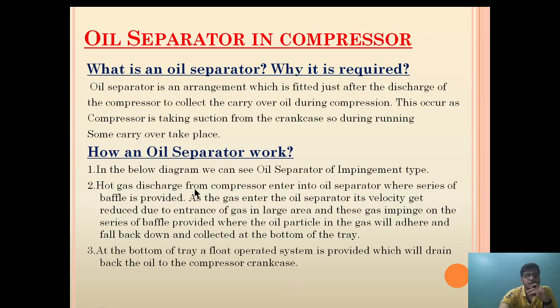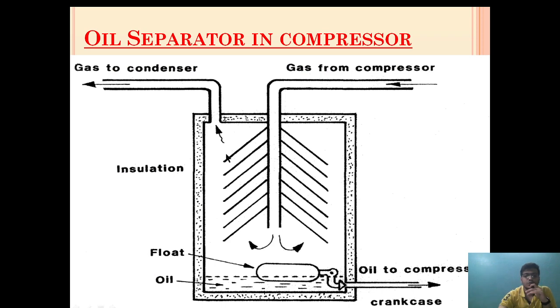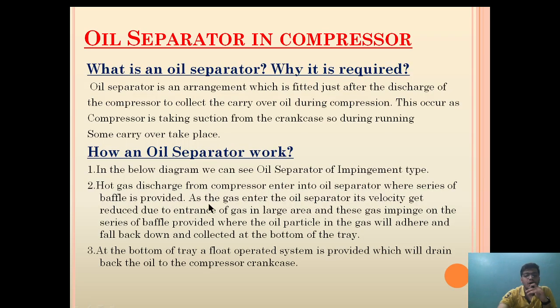Hot gas discharged from the compressor enters the oil separator where a series of baffles is provided. As the gas enters the oil separator, its velocity is reduced due to the gas entering a larger area. The gas impinges on the series of baffles, and the oil particles in the gas adhere to the baffles and fall back down, where they are collected at the bottom of the tray.